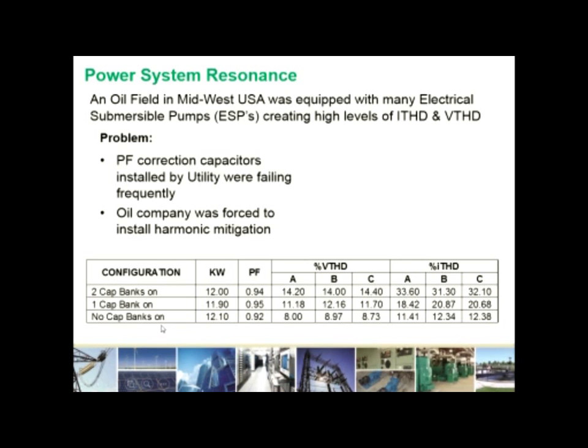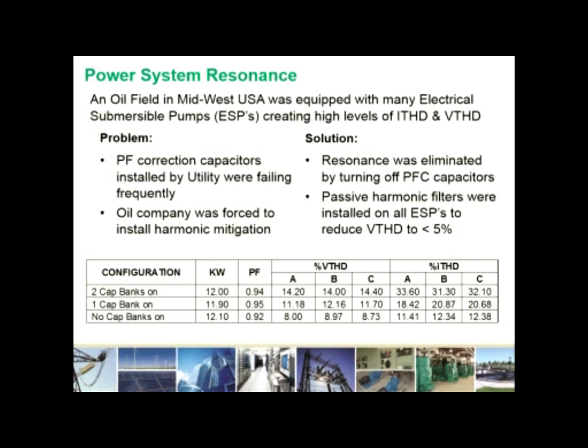When they turned all the capacitor banks off, both sets, the voltage distortion dropped to between 8 and 9%. So still high, relatively speaking, because IEEE 519 requires that voltage distortion levels remain below 5%, so it was still above that and still required harmonic mitigation. But we were starting at a much lower level than at the 14%. So by removing the power factor correction capacitors, we eliminated the power system resonance, and then by adding harmonic filters to the electrical submersible pumps, we were able to improve the power system voltage distortion to much less than 5%.